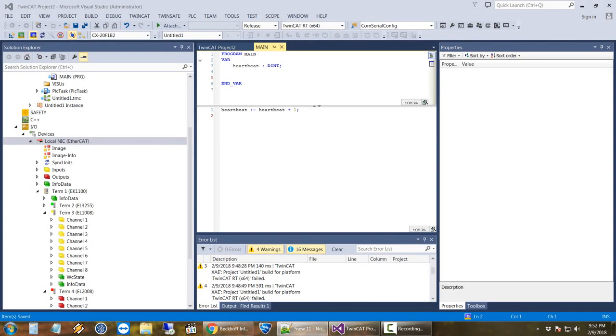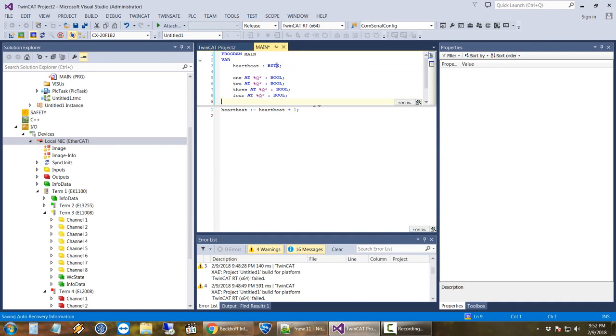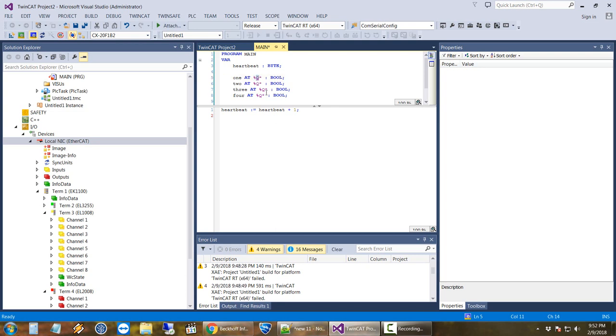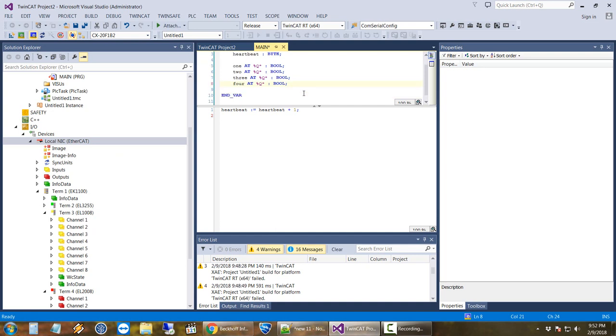Okay, so I'm back in our main program. And I wrote a little bit of code offline just to save the typing. And essentially what I've done here is converted heartbeat over to a byte, which I'll explain in a minute. One here is just a bunch of bits basically, just booleans. And those booleans are either true or false. And then this is kind of the magic part here. It looks a little bit confusing, but you're just saying that one exists at the memory address, Q. And Q means the output memory space. There's only a Q and I, so don't let that stress you out. And then star is where you normally would put the memory address. But rather than dealing with that all on your own, star just says let this mapping system kind of handle that for you. And then you don't have to worry about shifting addresses. And I think for a long time people had to put these in back on older PLCs. But on this you don't have to anymore, so I'm not going to.